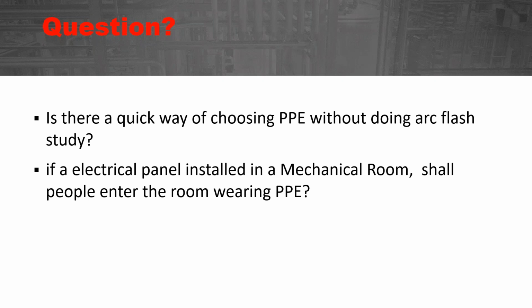You would test for the absence of voltage phase to phase and phase to ground, then test the tester again. And as long as you've gone through all the other steps, a total of 8 steps, with 7, you might not be using step number 8, depending on the voltage. But as long as you go through all of the steps and have established and verified that equipment is in an electrically safe work condition, and it can be done from the outside, then you could open up the equipment without wearing arc-rated PPE and shock PPE.